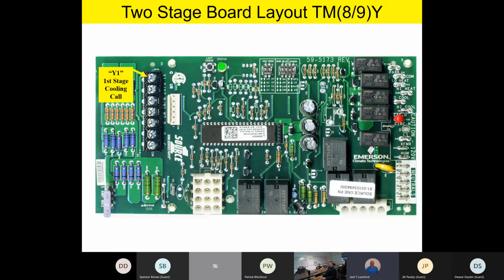It's a good furnace. As a matter of fact, if I had natural gas on my property, this is probably the furnace I would put in. I really, really like the features of this furnace. So Y1 is our first stage cooling call. Y2 will be our second stage cooling call if we have a 2-stage product outside. W1 is our first stage heating call.